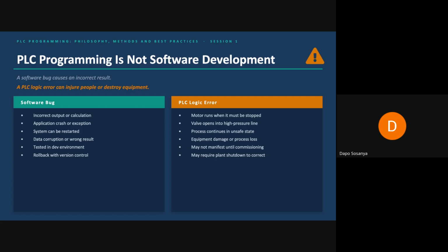But then a logic error, probably a timed logic error or a dynamic error somewhere, just initiated heating of that process. What you realize is that you have destroyed that batch because you have interrupted the fermentation process.